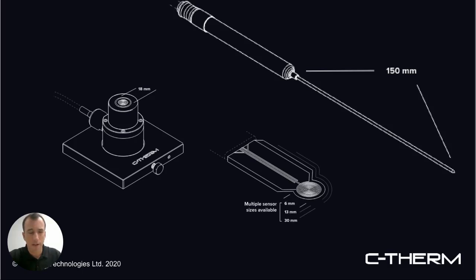This just gives you a little bit of idea of what those sensors look like in terms of size. It helps inform the minimum sample requirements for running a test. You see that the largest sensor is the needle probe. The active area of the sensor is 150 millimeters in length, and you have to fully cover that area with the sample material. So if you've got a really expensive material, or you're in a development phase, this is not the best method to run because you need a larger volume of it.